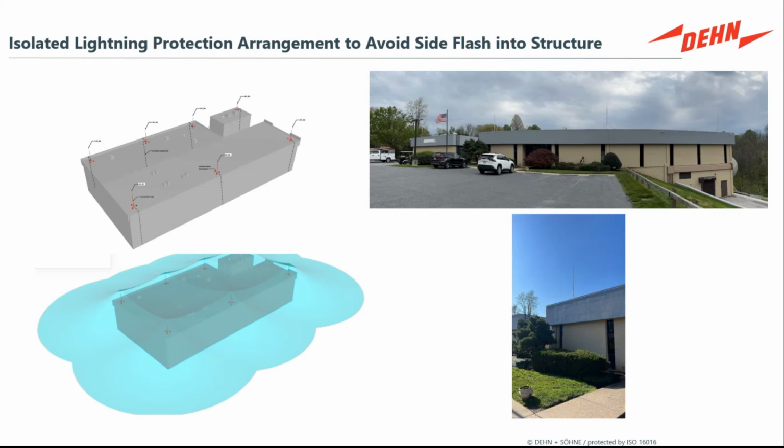We like to show the rolling sphere methods applied as accurately as possible on the site conditions to make sure that we've accounted for things like these separate outbound generator buildings. And these are mechanically separate from the structure, but electrically connected. So it's all one part of the larger infrastructure.